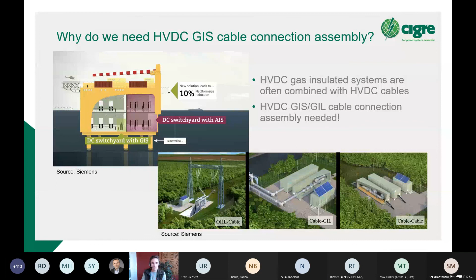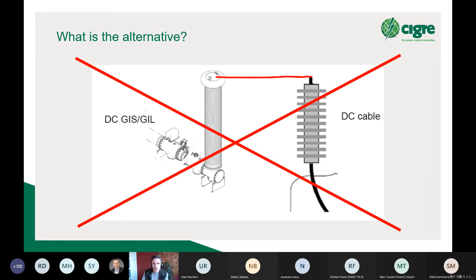And this brings a bit of a problem, because if we don't have a proper cable interface, then we end up with something like this, where we have to use a connection through air, with an air termination on the cable and an air termination on the GIS. And this would kind of defeat the whole purpose of having a GIS, because this, of course, takes a lot of space.